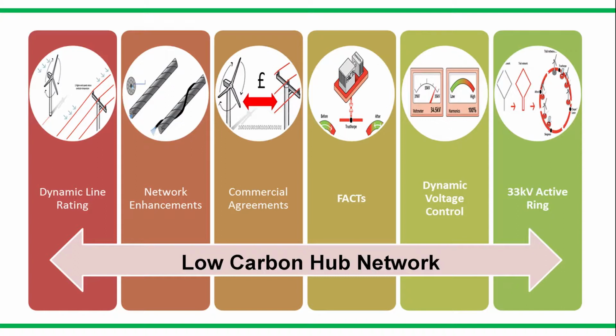We're also doing dynamic voltage control. As we mentioned earlier, voltage rise is one of the limiting factors of DG connections. Our voltage is controlled at Skegness for this entire primary network and around, and it's set as one setting for 365 days a year, 24 hours a day. So we set it up pretty much for worst case, which is maximum generation, minimum demand with a set point, which means during those conditions, the network will all be within statutory limits with a certain bandwidth.